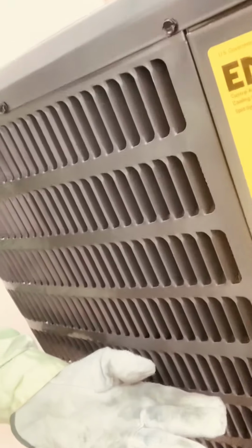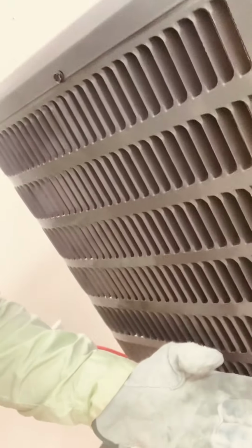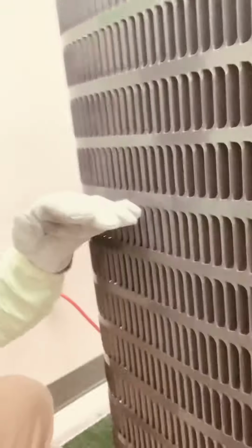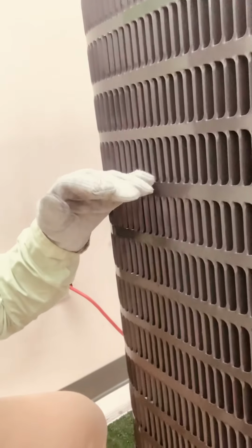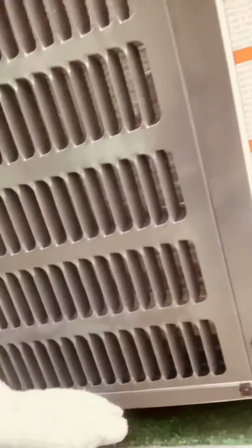And by the time it gets midway of the condenser coil, it's going to be saturated. Now, what is saturated? Saturated means it's a mixture of liquid and vapor refrigerant. By the time it gets to the bottom of the condenser coil, I'm going to be 100% liquid. And how do we know that we're 100%? We're going to do a formula. That formula is called the subcooling formula.